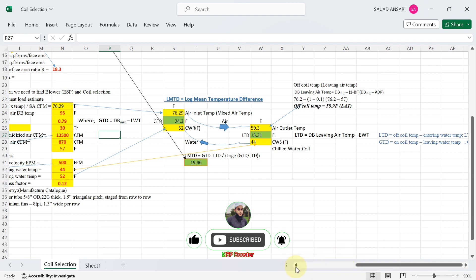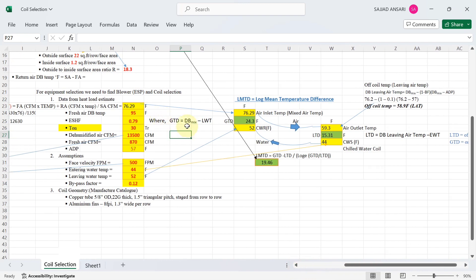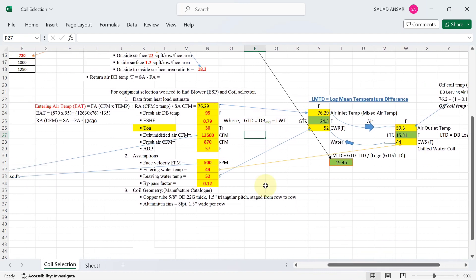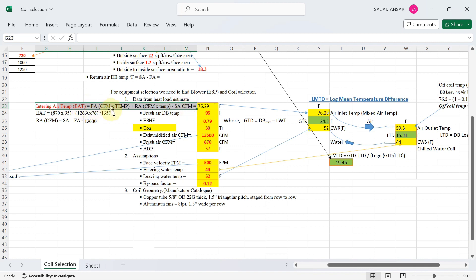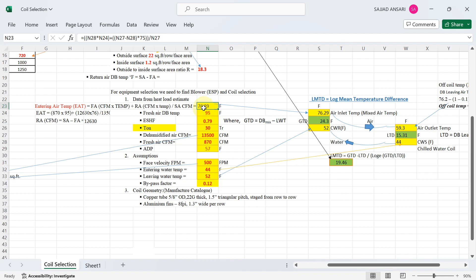DB mix means the on-coil or entering air temperature. Leaving water temperature is 52°F. To calculate the on-coil (entering air) temperature, the formula is: (Fresh air CFM × fresh air temperature + return air CFM × return air temperature) ÷ supply air CFM. Using all values from the heat load calculation, you get approximately 76.29°F entering air temperature.